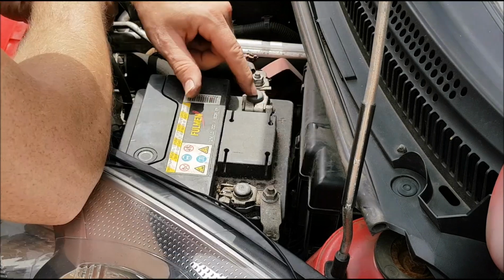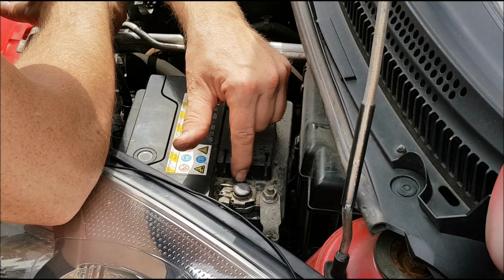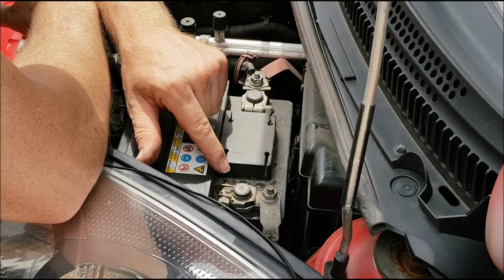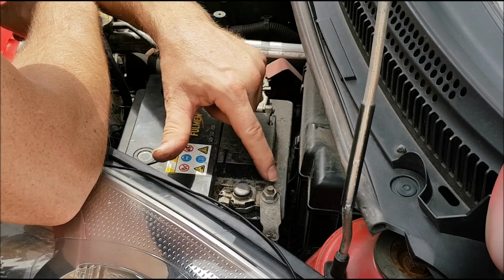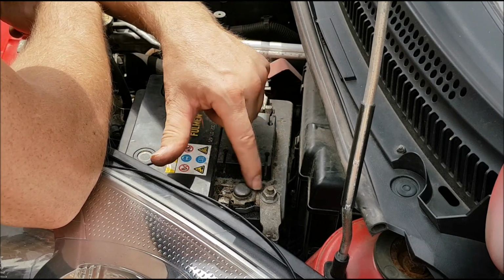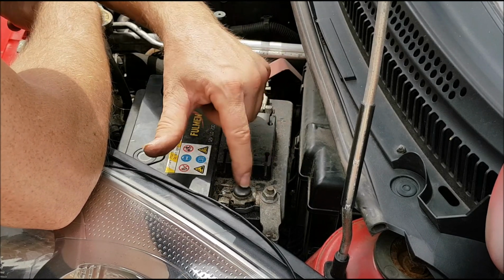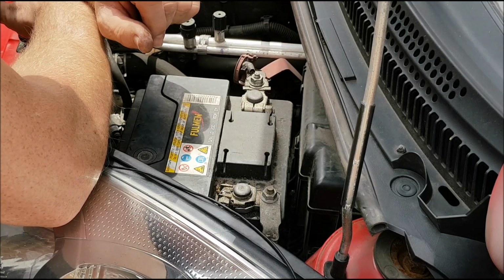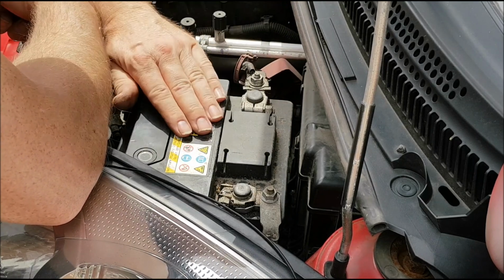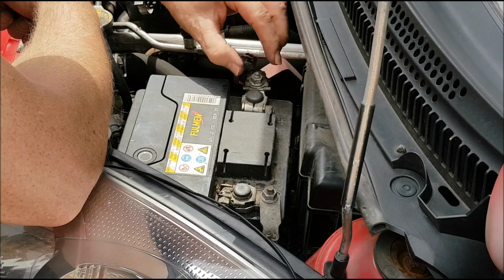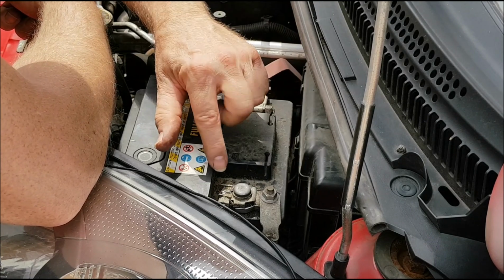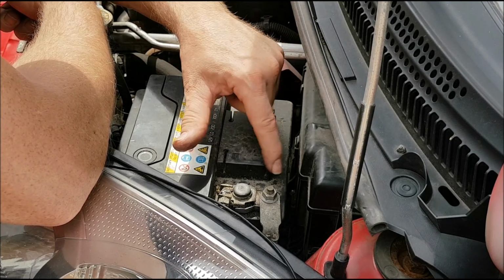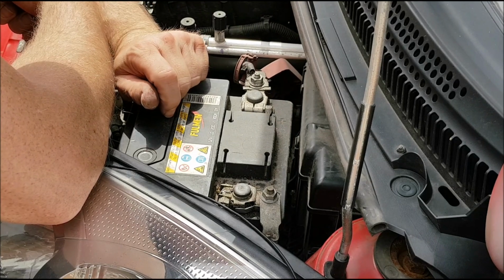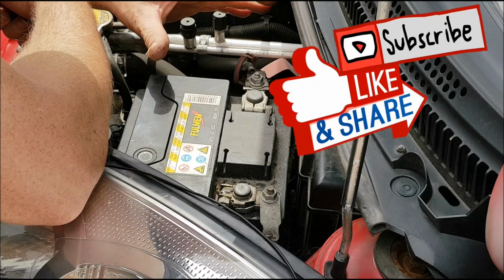14 millivolts. What that means is that we've got a voltage running across the top of the battery through the dirt and any grease and oil on the top surface. Because there's a voltage running through there, there must also be a current running through there. That means the battery is constantly draining a few milliamps through the dirt on top of the battery. That's why it's important to keep the top of the battery clean.